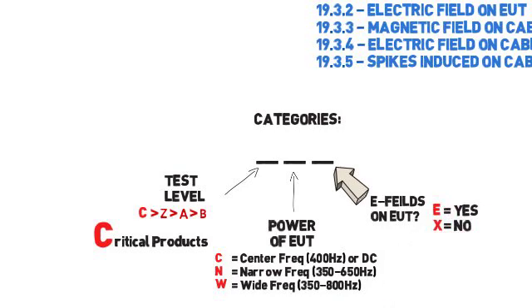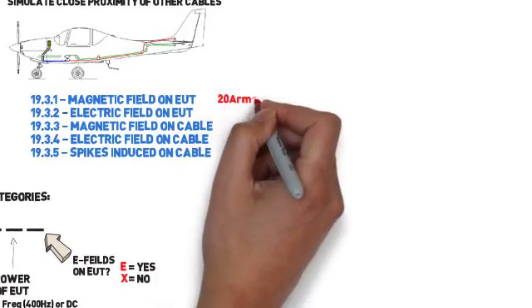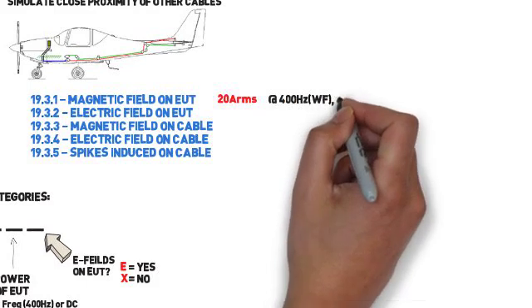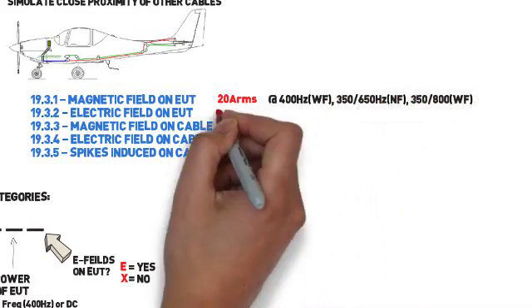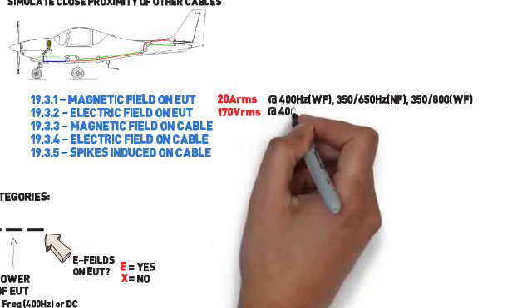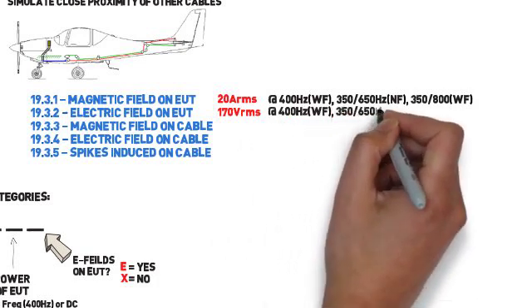The test level for magnetic fields is run at 20 amps regardless of your category, with the frequency determined by the second letter of your category. Electric fields is run at 170 volts regardless of your category, again with the frequency determined by the second letter.